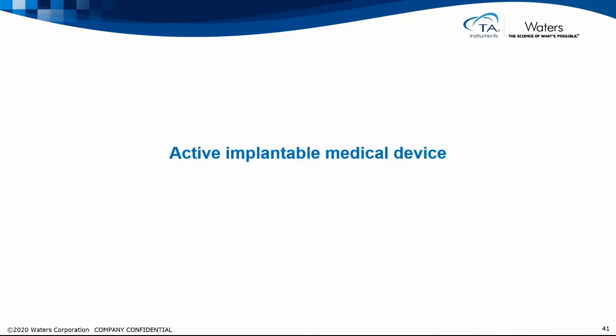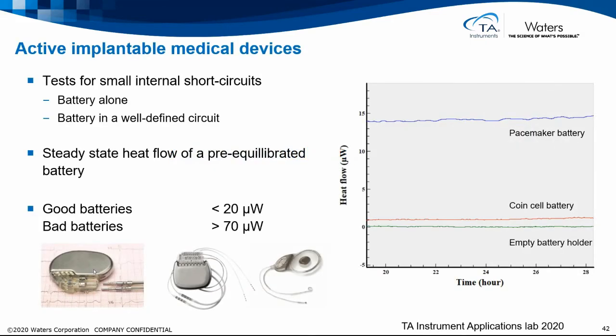And the final example is on active implantable medical devices, which could be pacemaker batteries, and it's very important that these work without any problem once they are put into a patient's body. So tests can be made for small internal short circuits. It could be done on the battery alone or a battery in a well-defined circuit. Typically, this measurement is done as steady state heat flow of a pre-equilibrated battery. So it's equilibrated at 37 degrees and then put into the calorimeter, measure heat flow and remove it.